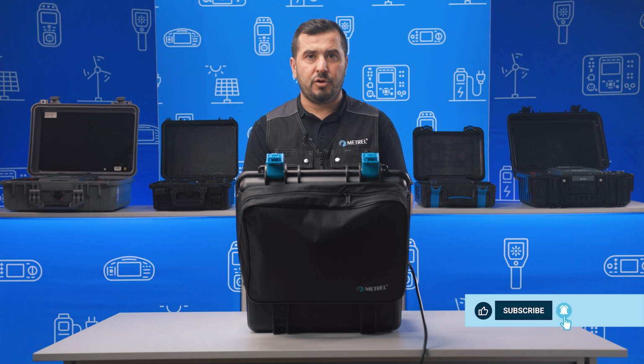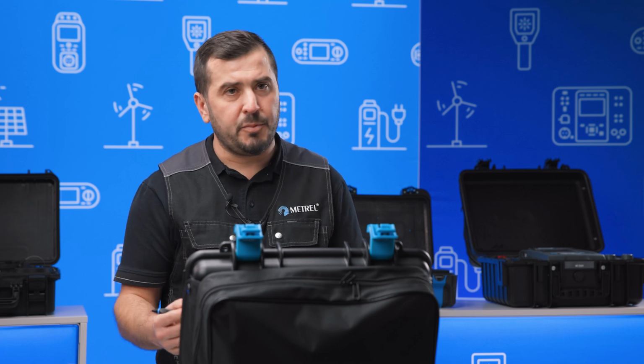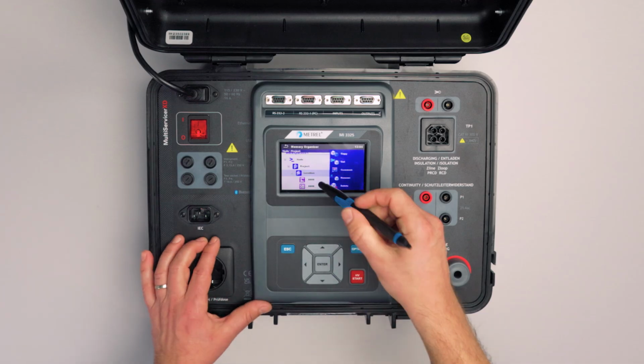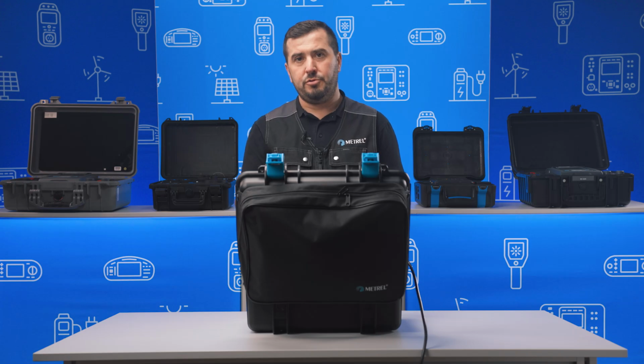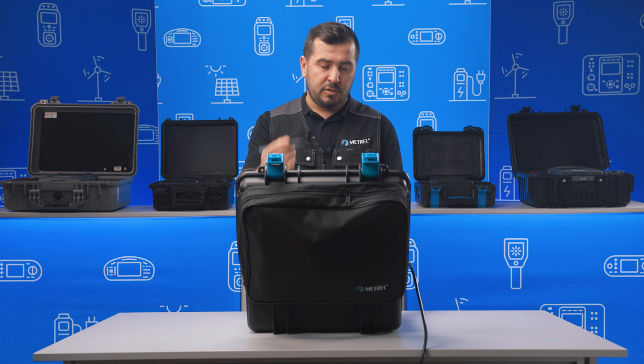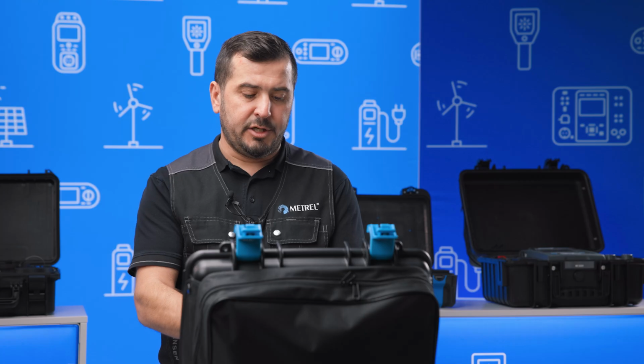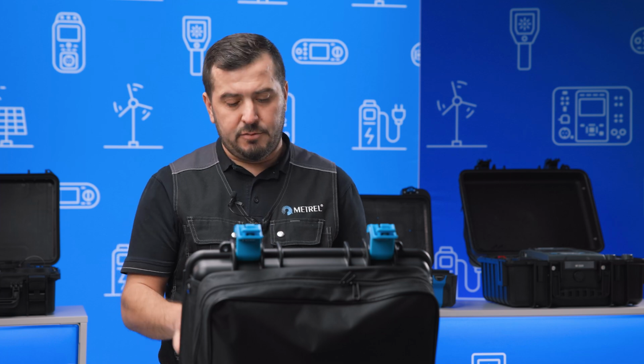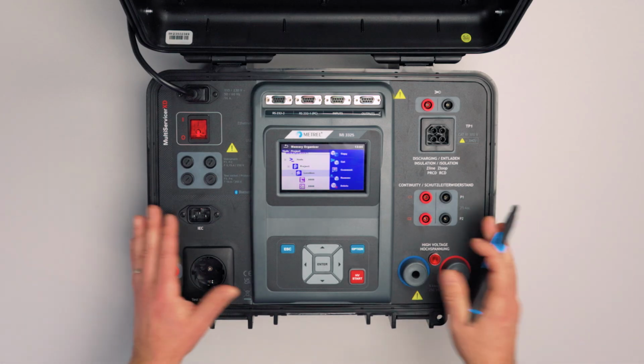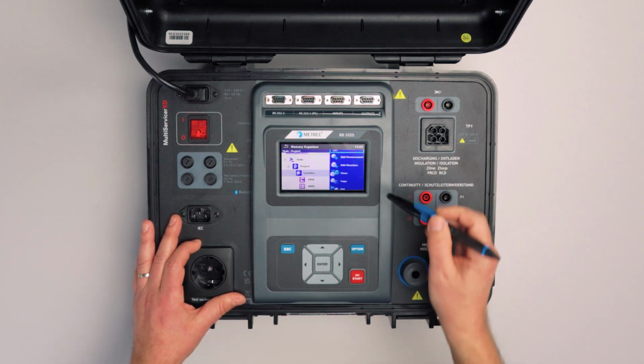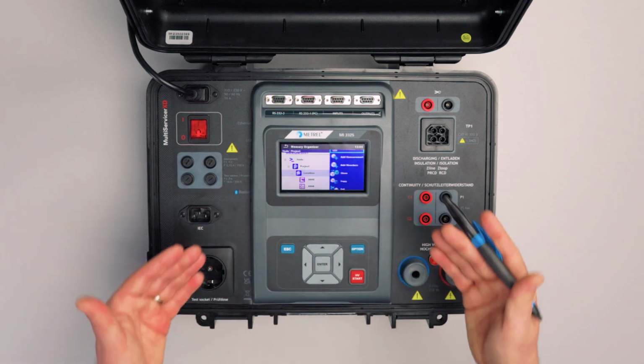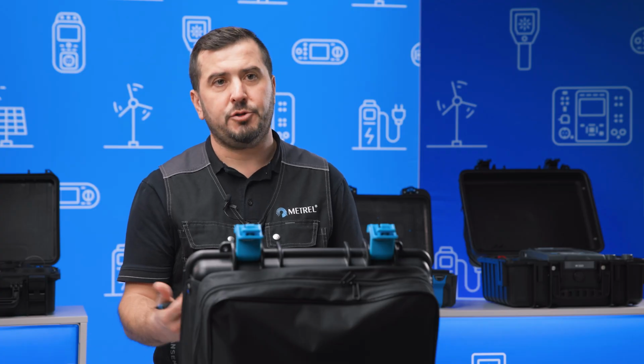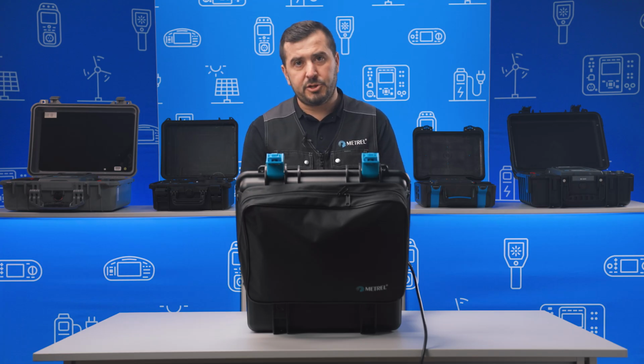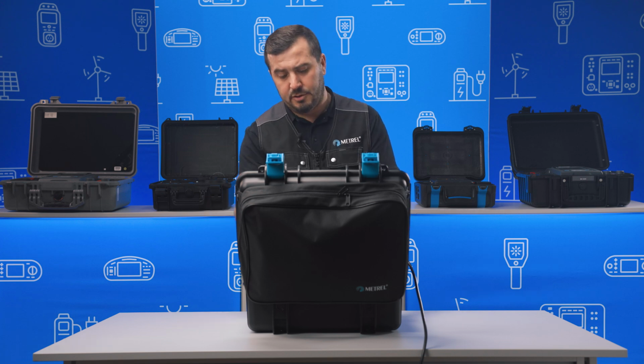also copy it or clone it. So cloning is a very fast way of performing tests on similar equipment, let's say. We can start creating a test structure on the instrument for a new type of machine, and also execute the tests during this creation of the structure. And after we finish, and we would like to test similar or the same type of electrical equipment, we simply use the option clone, and the instrument will clone the complete structure, of course without executed measurements. So the next equipment that we go and test, we just follow the measurement steps from the previously tested equipment.